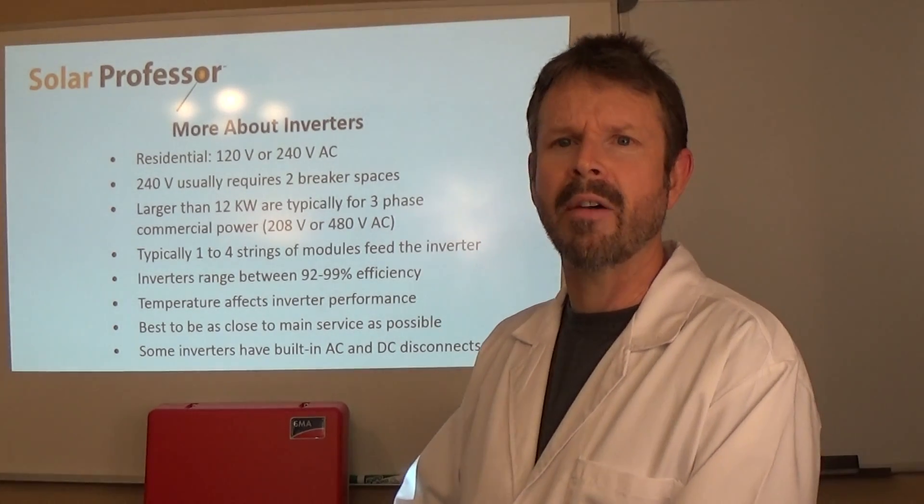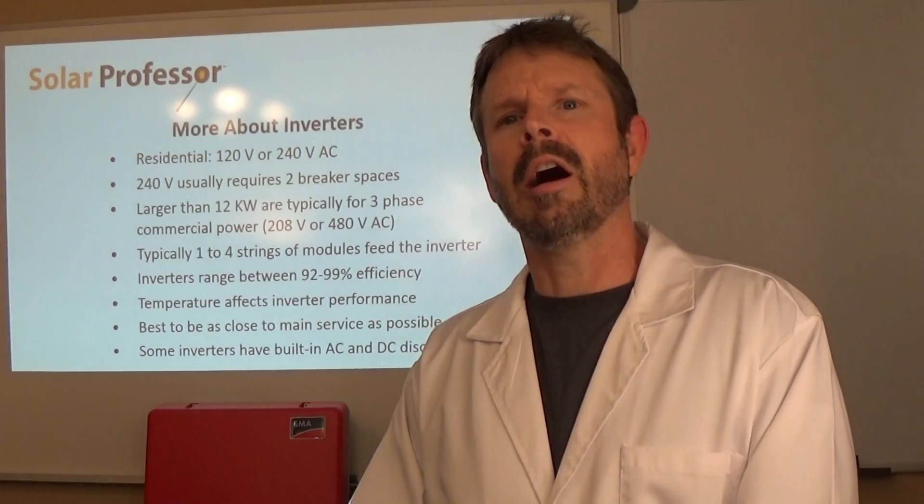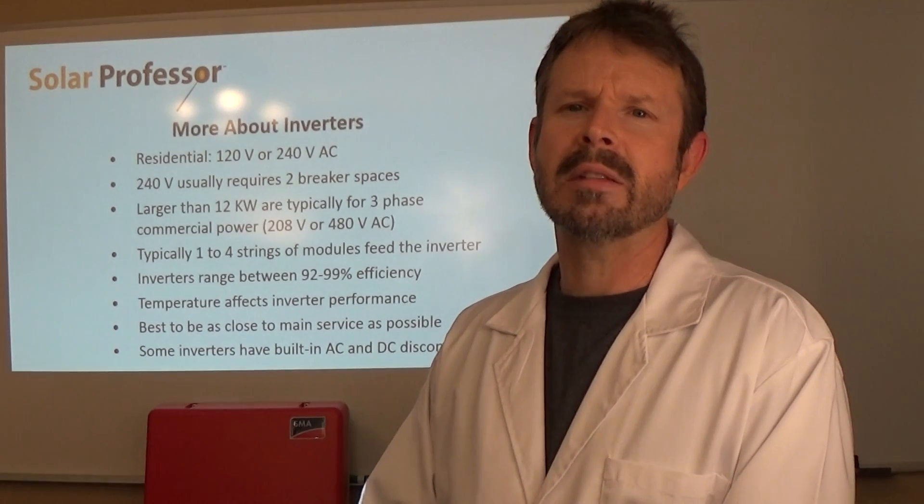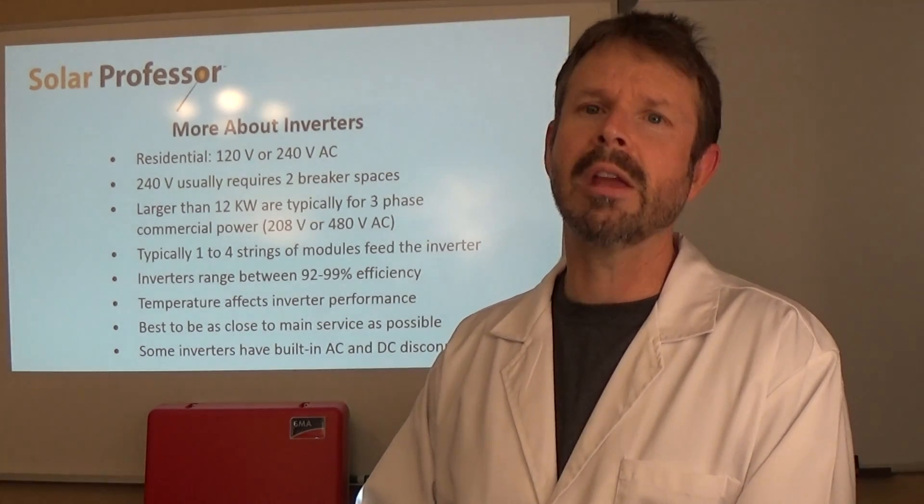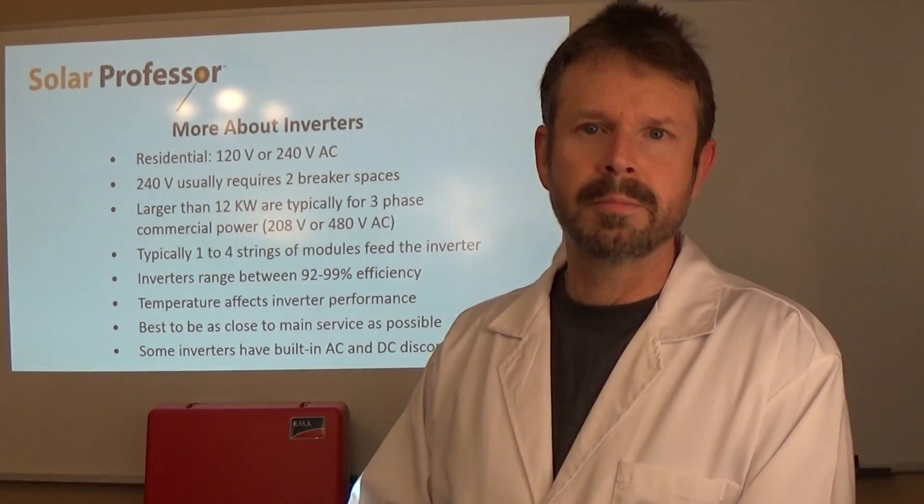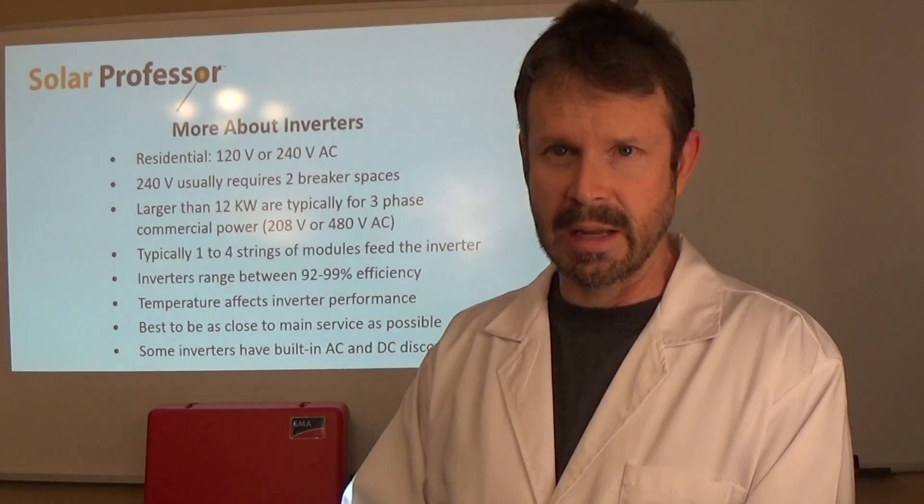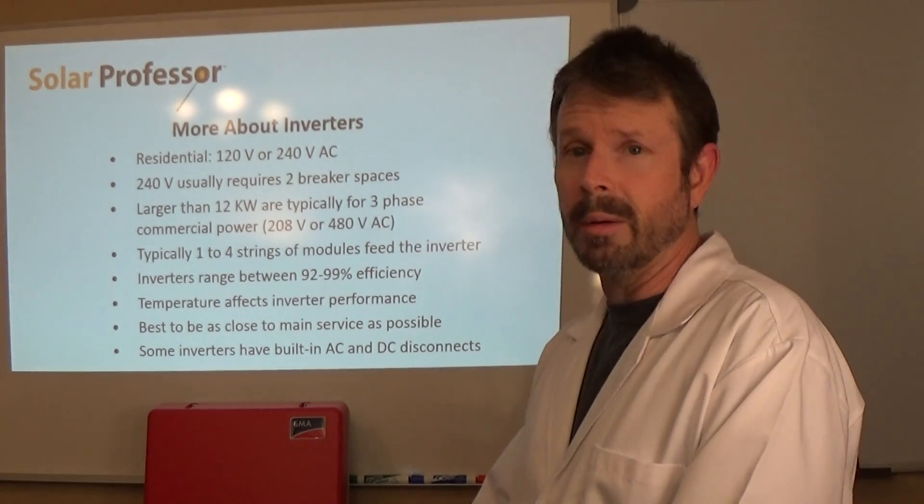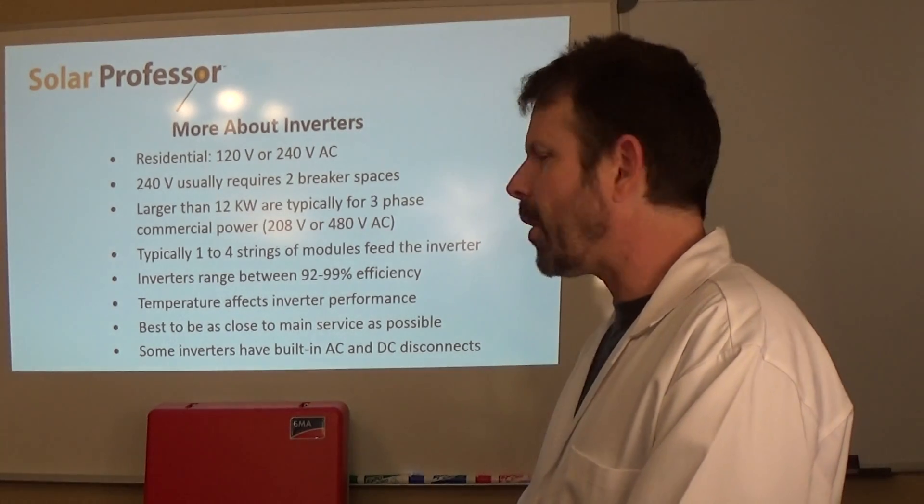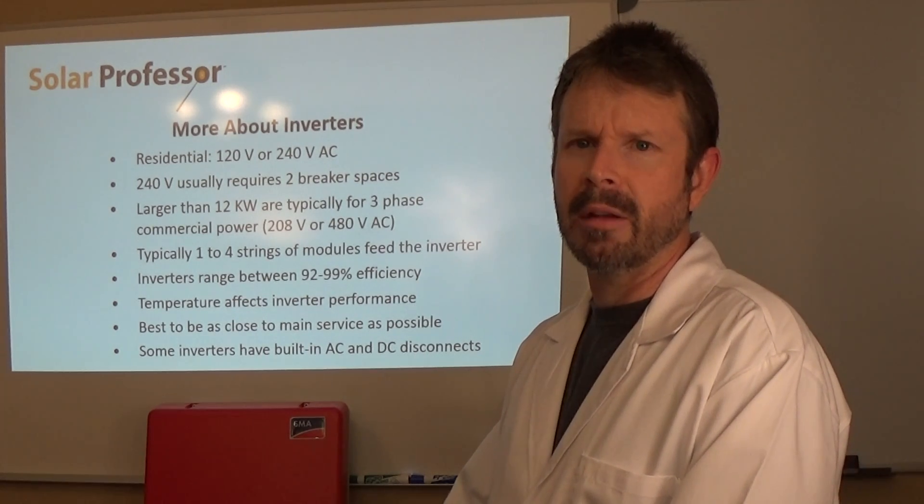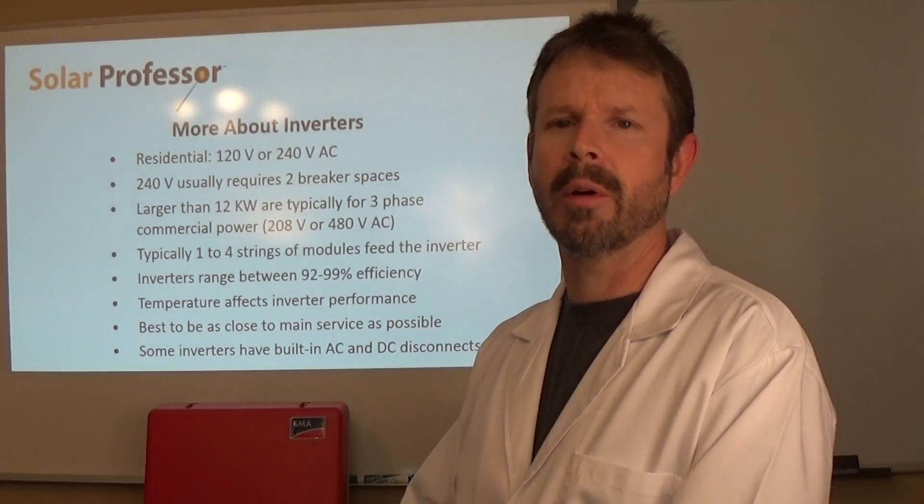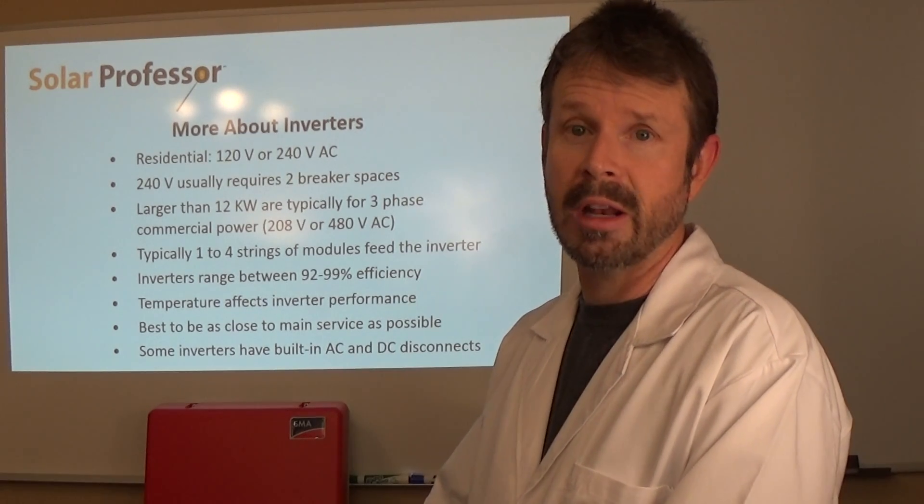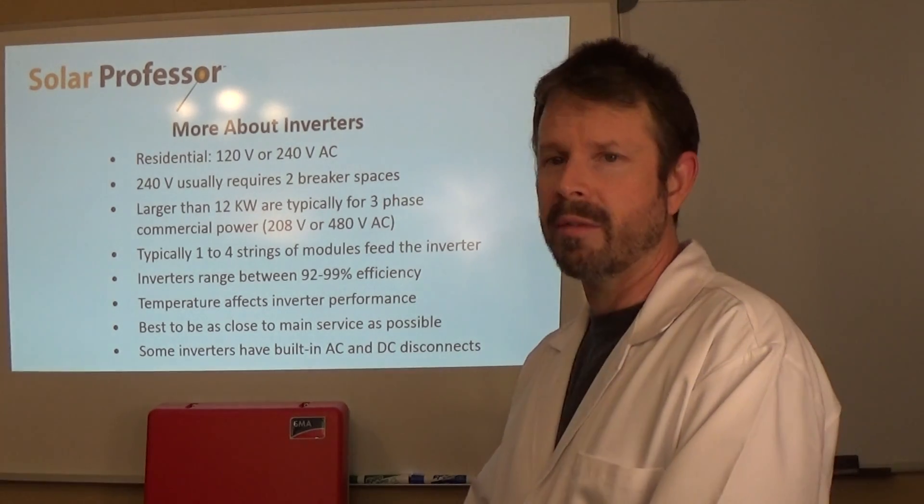Temperature affects inverter performance. The hotter it is, the less output the inverter is going to have. I've seen inverters mounted directly on the south side of a building in the sunlight, that's not the best approach. Inverters are pretty solid state, they'll handle heat, cold, crazy conditions like wind storms and sand storms, they're tested for that. But we want to do the best that we can to limit it overheating.